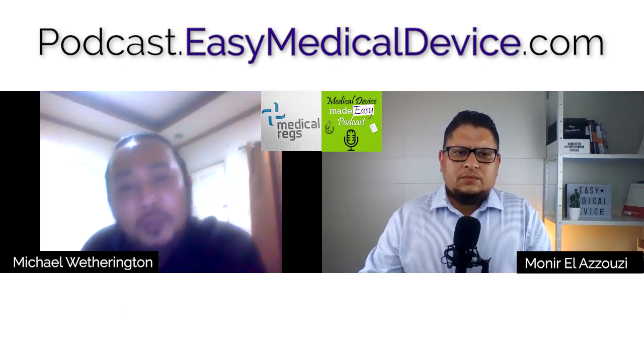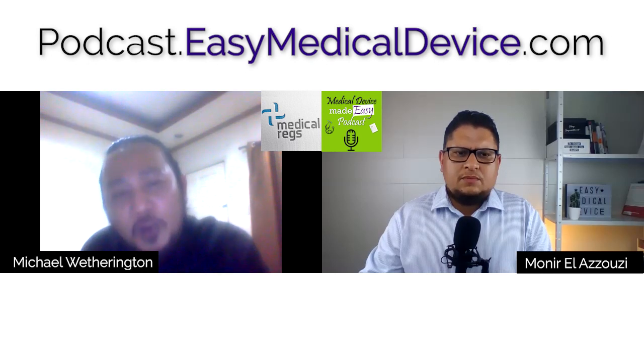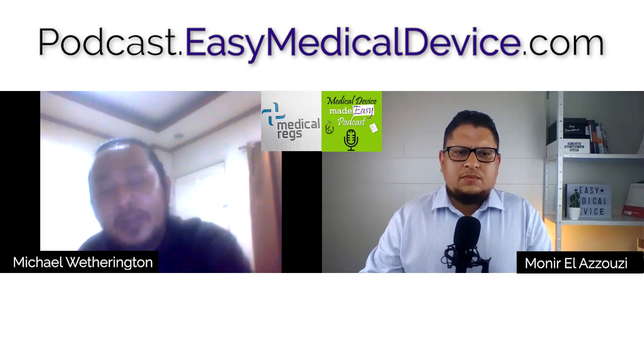So I don't know if that answered your question, but certainly you should have more freedom with your risk analysis. And just because EN 60601 exists doesn't mean that any electrically powered active device automatically falls within the standard, or that everything within the standard will apply. So you have to really know the content of that standard and be able to use specific requirements as a risk mitigation based on the hazards that you identified.